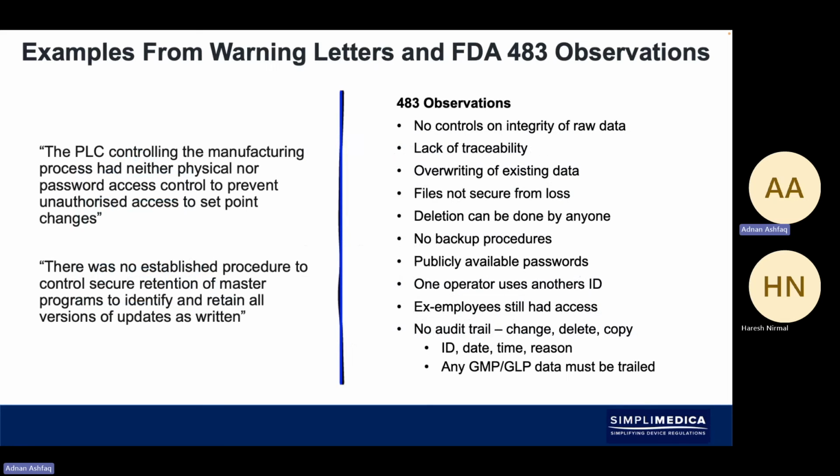I also wanted to share some examples of warning letters from the FDA. These are 483 observations. I think some of them are actually quite old. And here you've got an example where there have been 483s based on no controls on integrity of raw data, lack of traceability, overwriting of existing data, files not secure from loss.